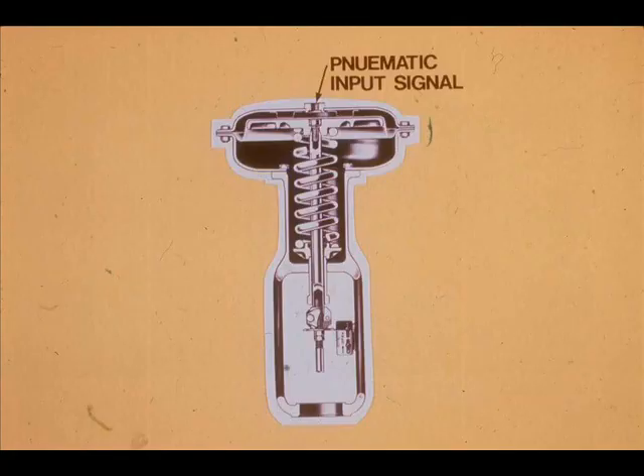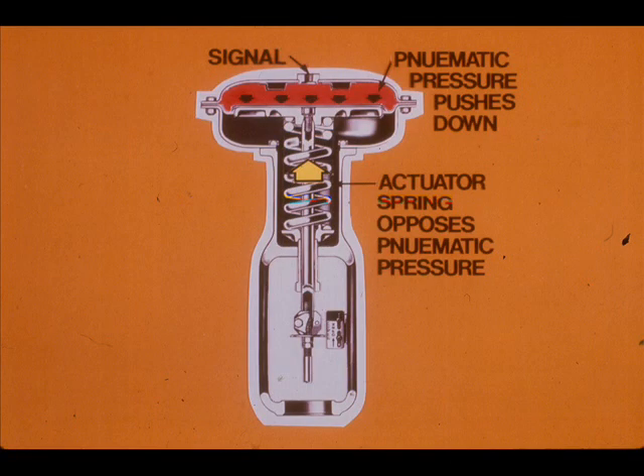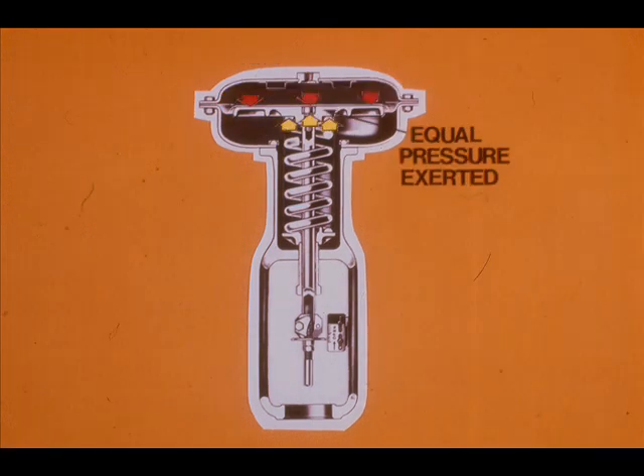The actuator operates as follows. The pneumatic signal, usually from 3 to 15 pounds, enters the upper diaphragm case. It forces the diaphragm down, opposing the spring. The actuator will move until the pressure on the diaphragm and the spring force are equal.